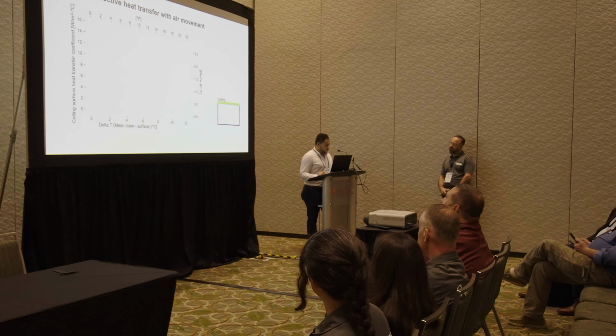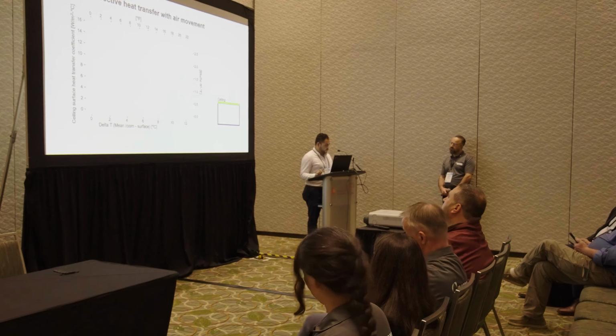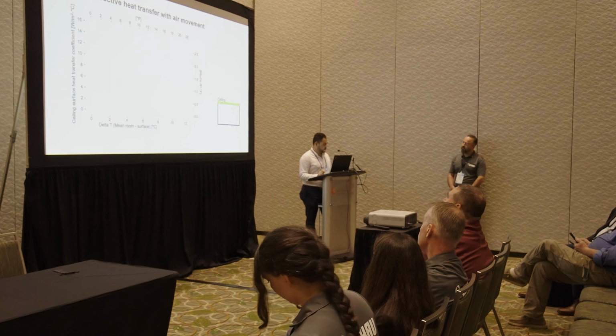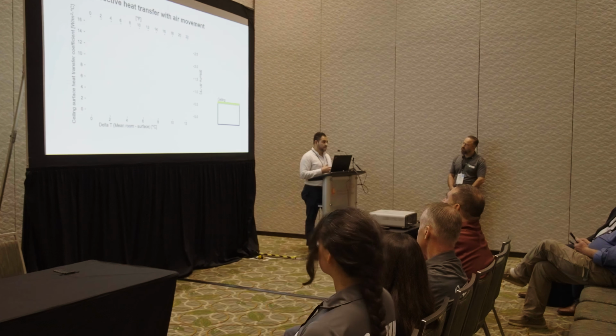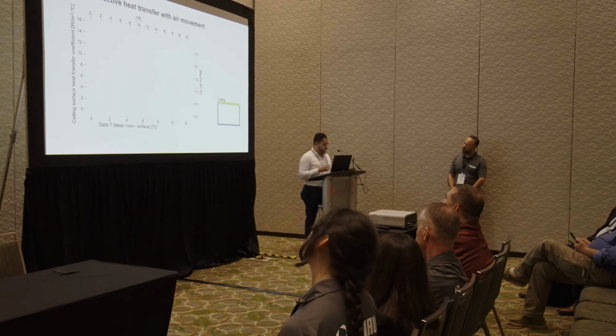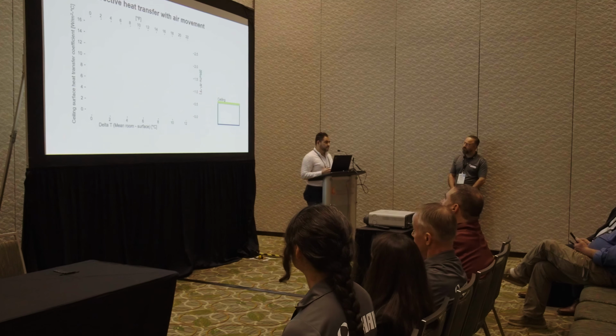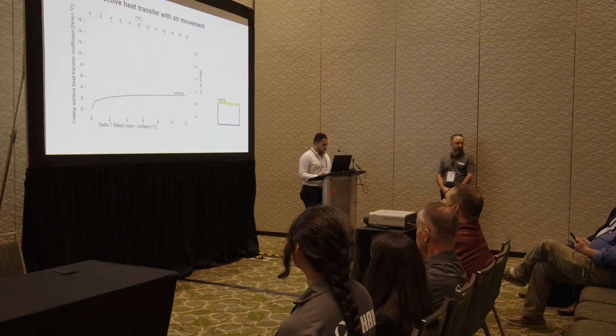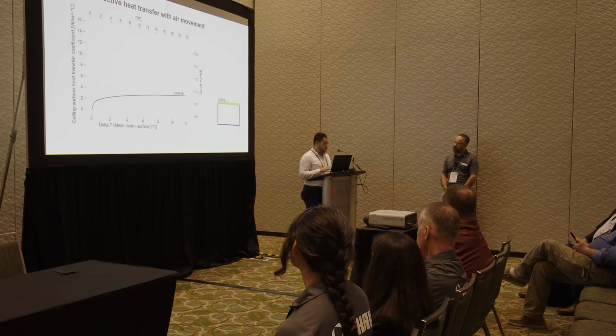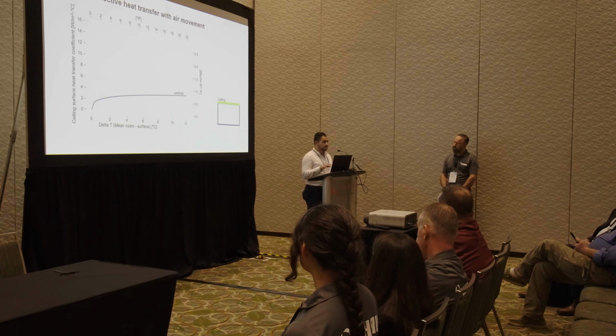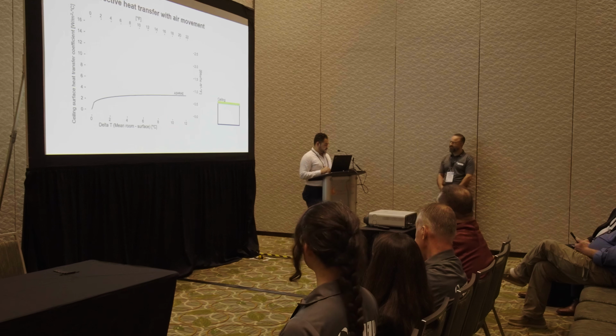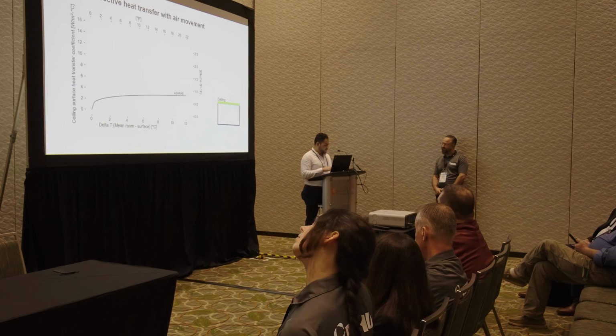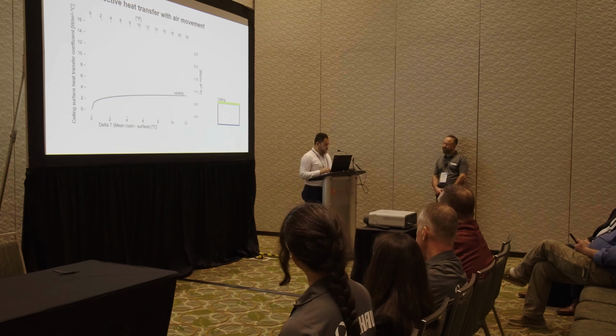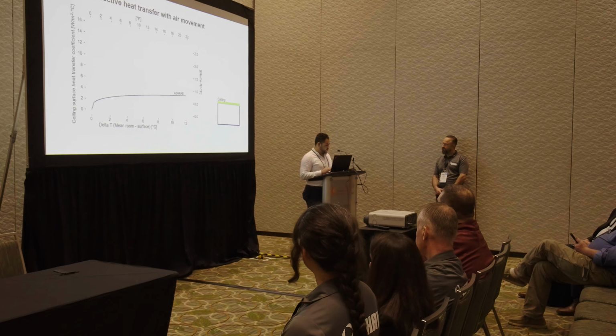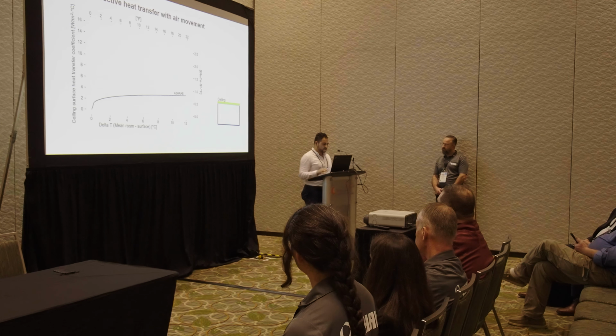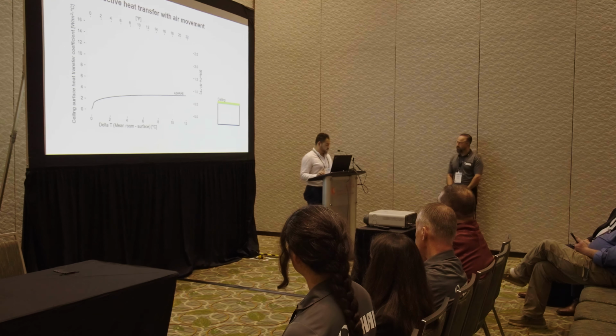So moving on to the main results of the CFD simulations, here's a plot where the x-axis is the temperature difference between the room air and the cooled surfaces, and on the y-axis we have the resulting convective surface coefficient. Before I start showing the results of the CFD simulations, let me anchor you with the ASHRAE guidelines for natural convection. In this case, where there's no fan, it shows an increasing coefficient with increasing temperature difference. So you see it just ramping up as the temperature difference gets greater.